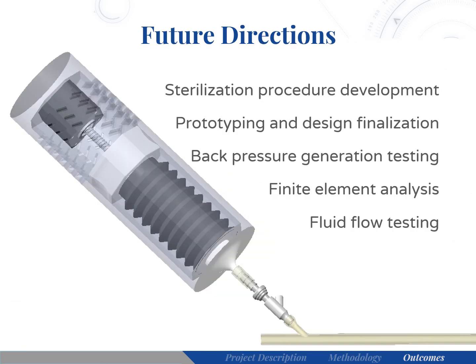Although faced with unfortunate and historical circumstances during this time, we as a team have developed a device that will mitigate the risk of CAUTIs. Future work to improve this device should focus on verification and validation benchtop tests, such as a back pressure generation test, finite element analysis, and fluid flow testing. Additionally, prototyping should continue and a sterilization procedure should be finalized.